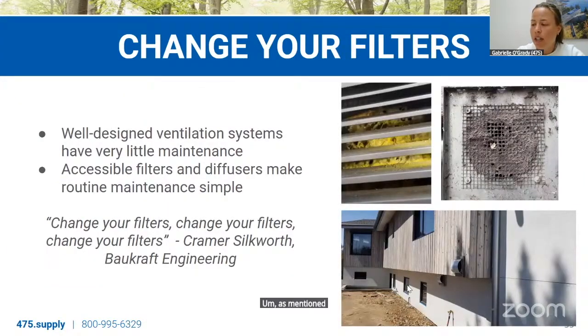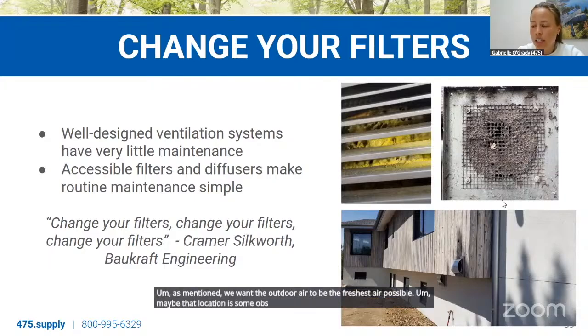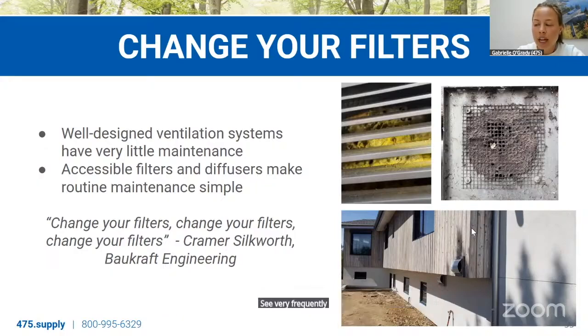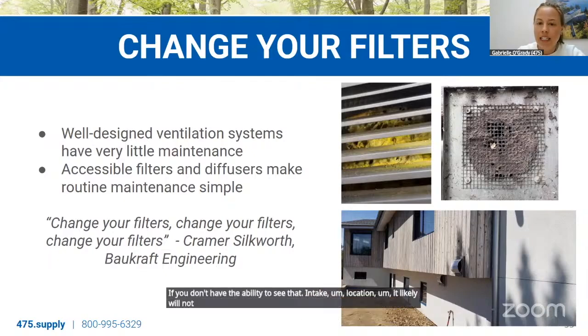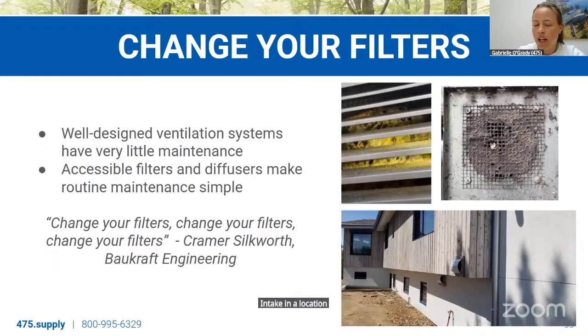As mentioned, we want the outdoor air to be the freshest air possible. Maybe that location is some obscure location that you won't see very frequently. Keep that in mind as well, because if you don't have the ability to see that intake location, it likely will not be cleaned as often as desired. So by placing the intake in a location that you pass all the time, that's easy to access, it's just going to make sure that that is maintained.